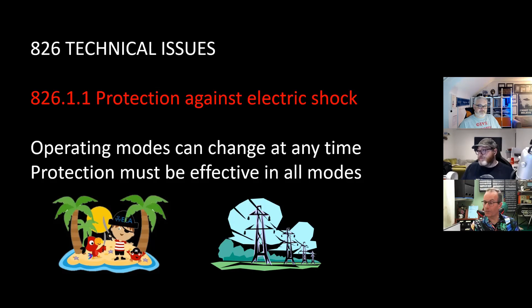So the earthing type may change depending on what mode you're in. If you go from feeding mode when you're connected to island mode, the proposals state that you will need an earth electrode, or more likely some kind of grid or mat, like what we've got shown there. You will disconnect from the public network, with all of the live conductors disconnected. Then there's another device called a neutral switching device, which connects the neutral and earth conductors together at the origin. The reason it needs this is because if it doesn't have it, none of the RCDs in the installation will actually work.